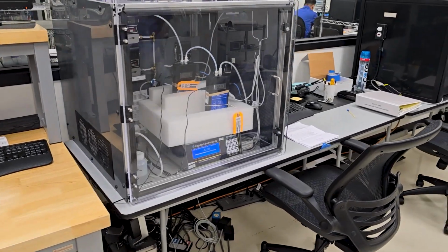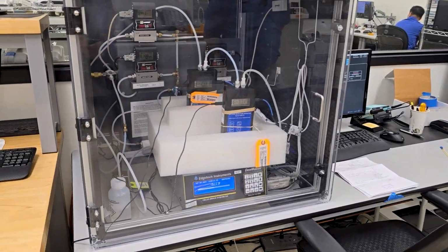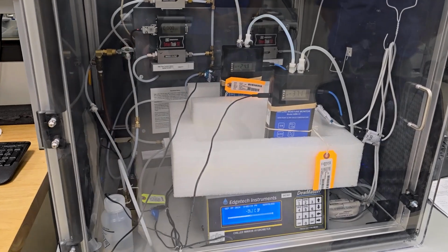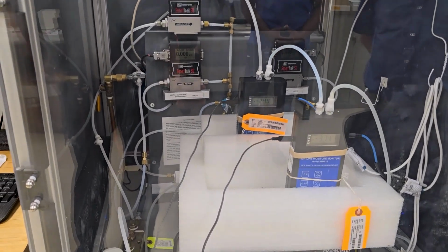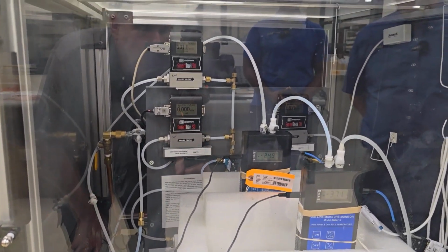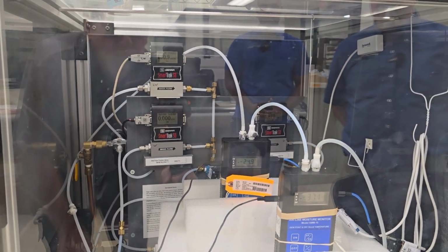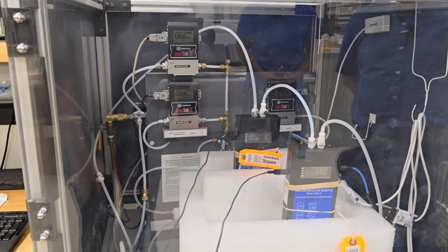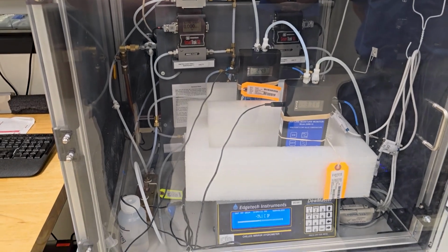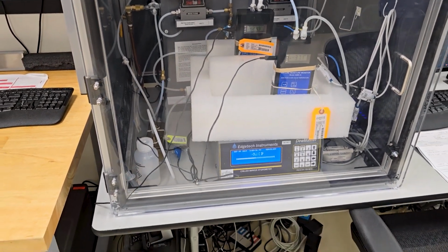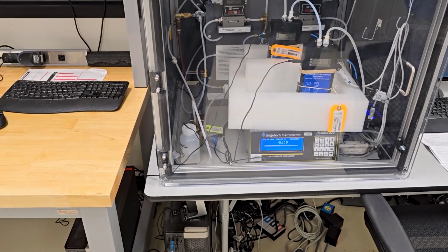Holy cow, look at this. Okay. So this is a fully automated station for humidity testing, airline moisture monitors. Even in the hospital, you've got your compressed air. You've got to make sure it's dry. Yeah. Well, how dry is it? Well, you need a meter for that. So we can calibrate those here with this automated station.